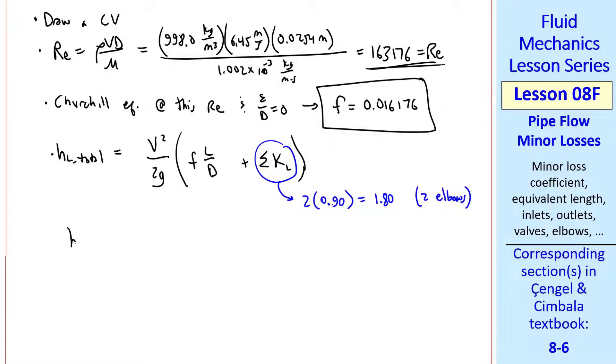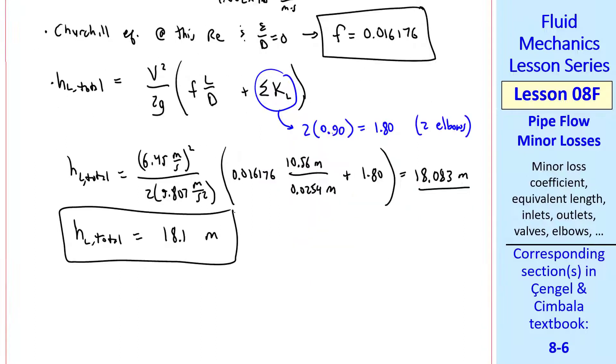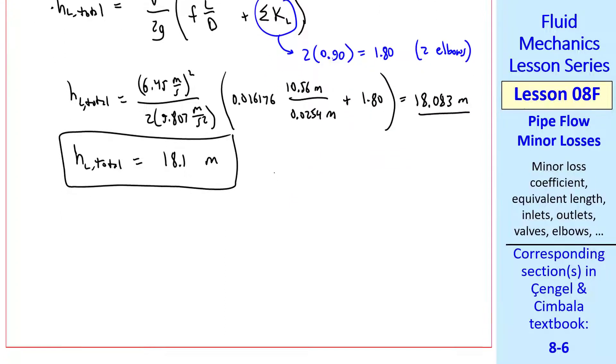So we can plug in the numbers. V squared over 2G F L over D plus sigma KL. I get 18.083 meters. So the three digits HL total is 18.1 meters.